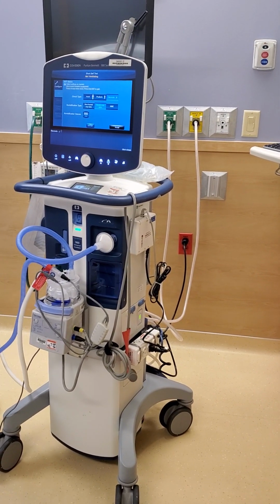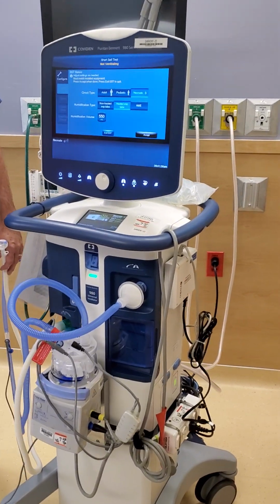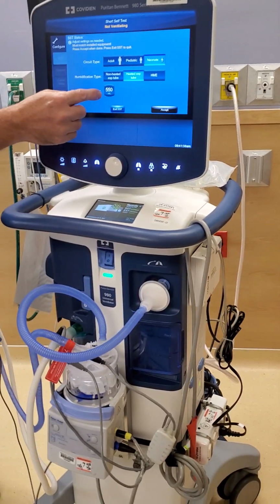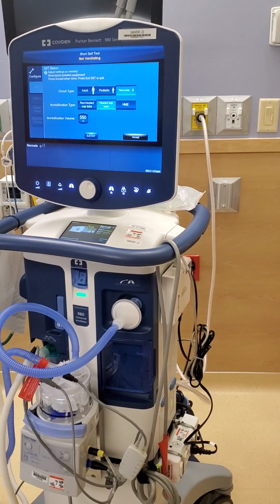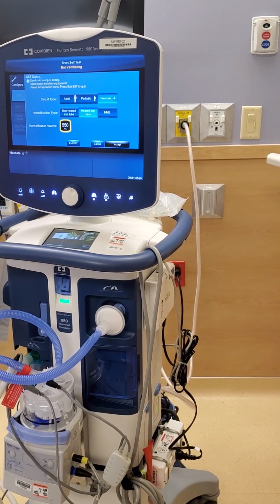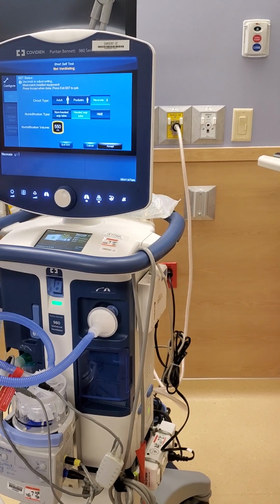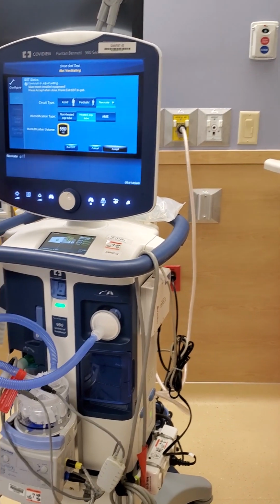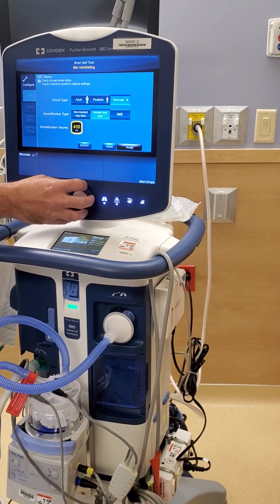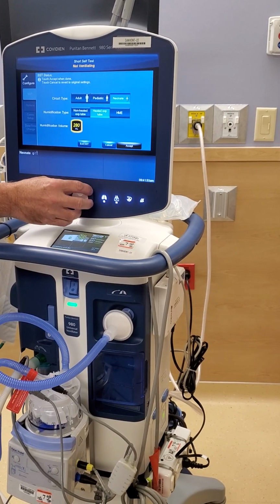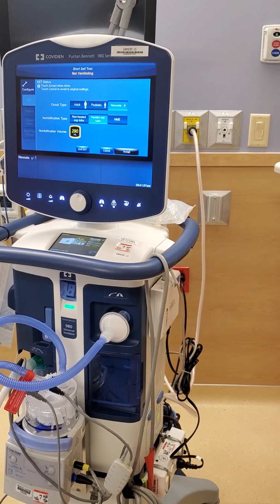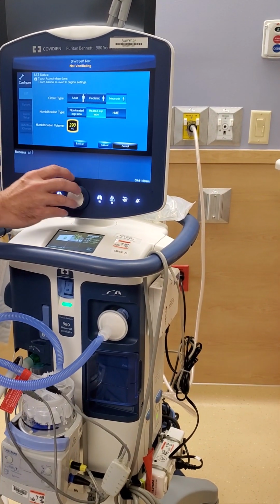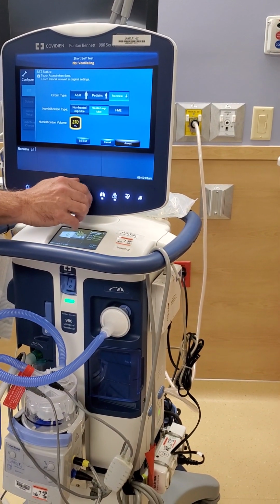All right. So here's the first most important thing. If it's a neonatal vent, if it was set up as a neonatal vent before, it should come up this way. And the important number is that one. On the adults, if you're taking an adult ventilator and converting it to a neonate, this is probably going to be set at 290, right? That's where we do the adult SST.